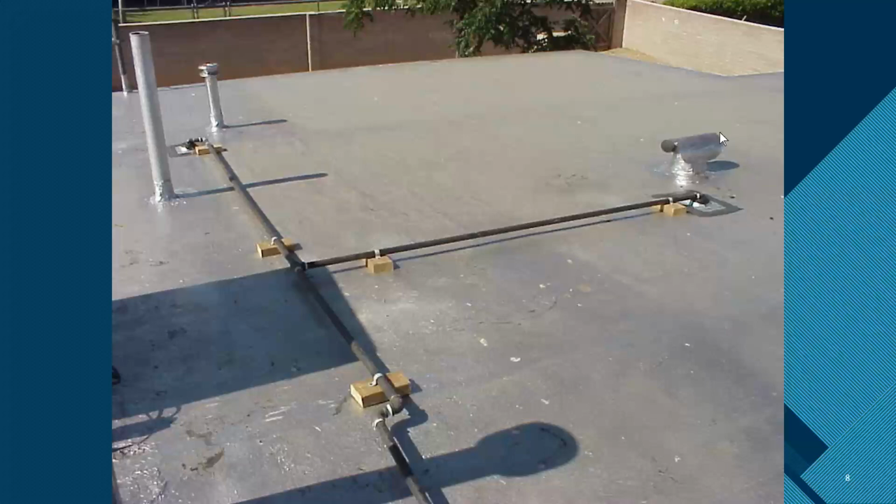Okay. You have a close-up of that so we can see that hub? I do. As we move along I'll show you that. Take a look right here. Here's a vent, most likely for the stove, and here's the gas line. You can't run more than one appliance off a 1/2 inch gas line.